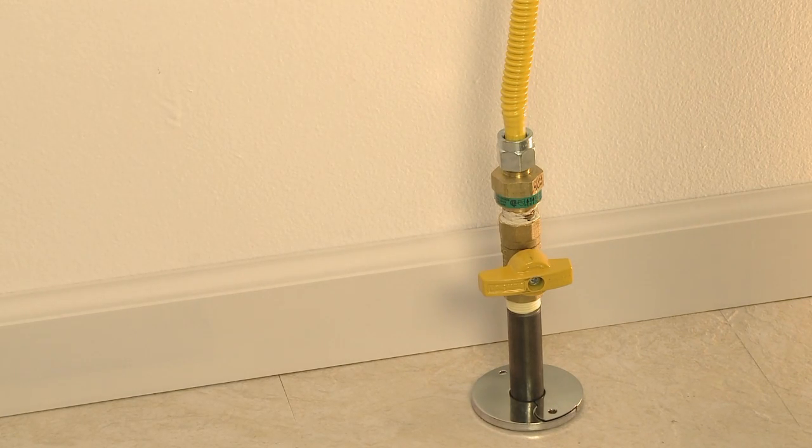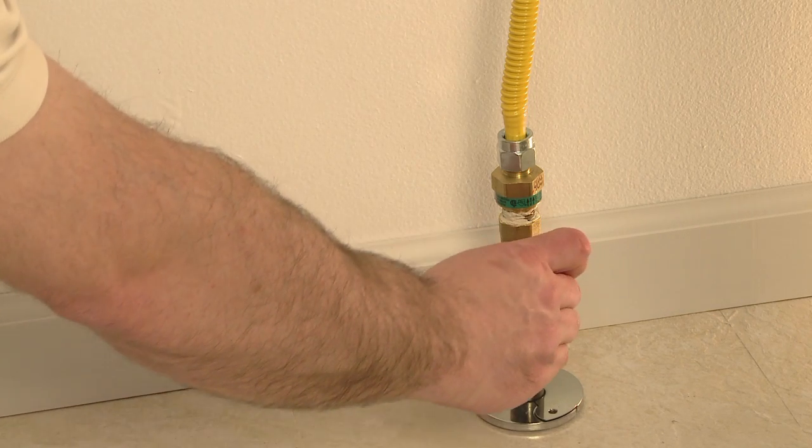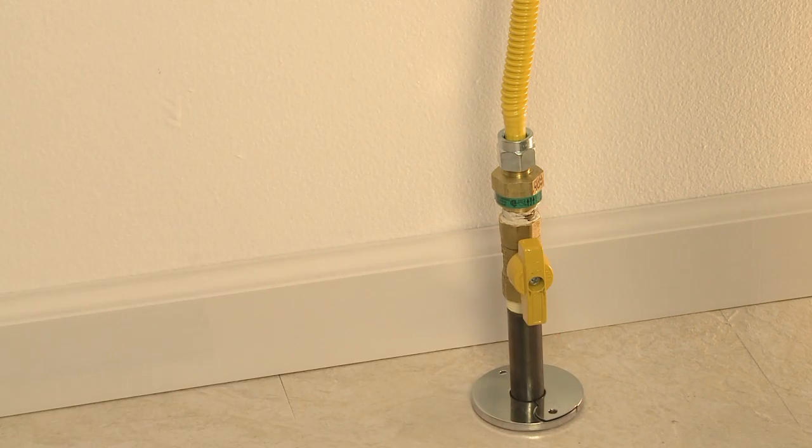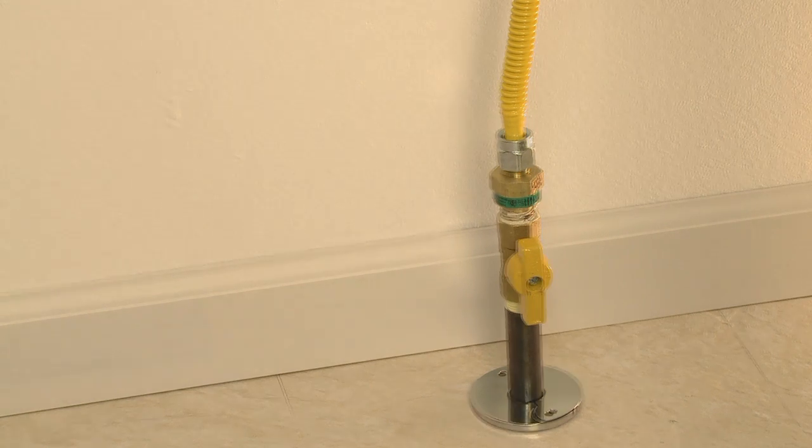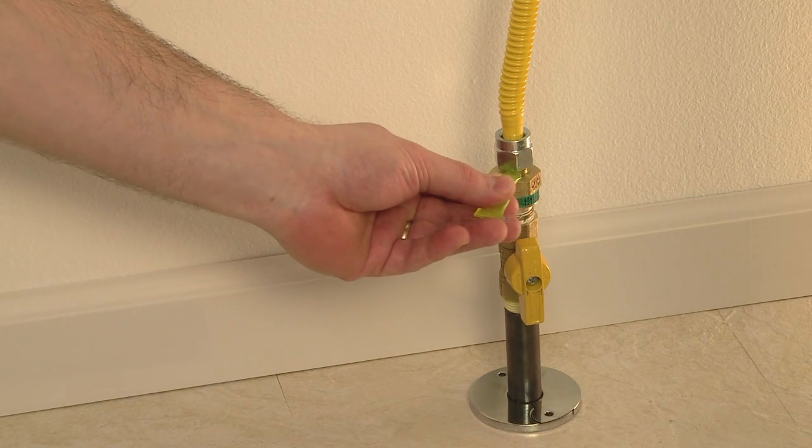It is important to check for leaks at this point. Slowly turn the gas shutoff valve back on by rotating the handle so that the handle lines up with the gas line. Place a generous amount of leak detection solution on all threaded connections.